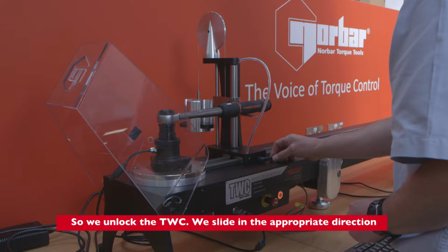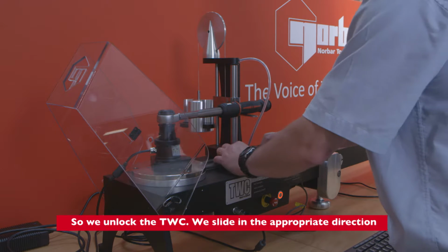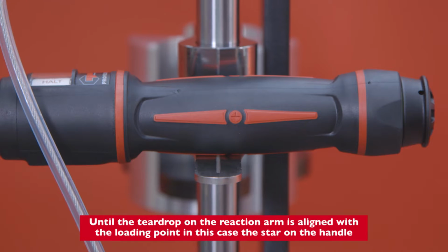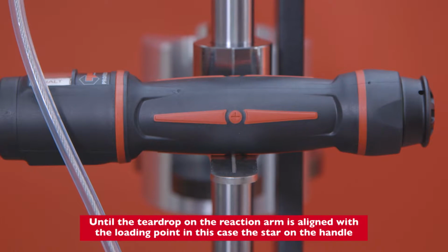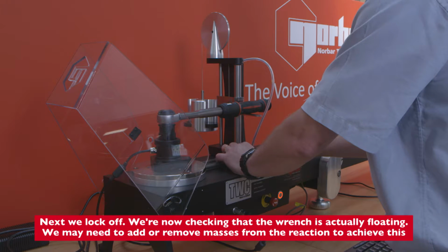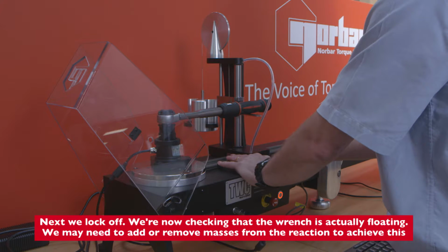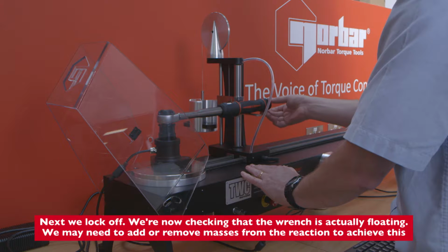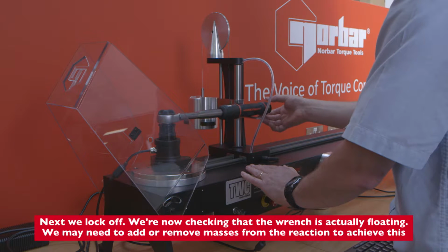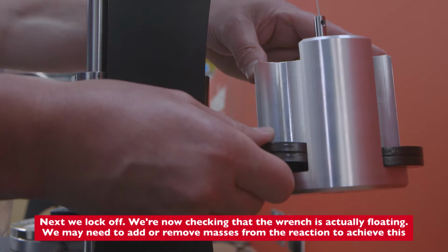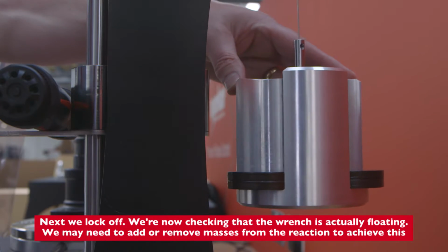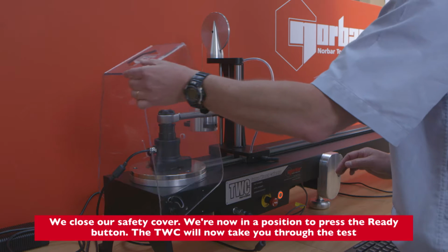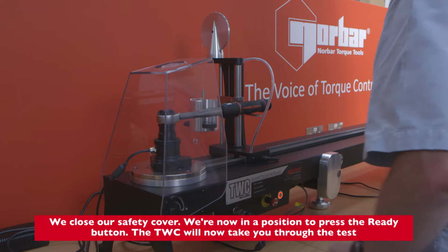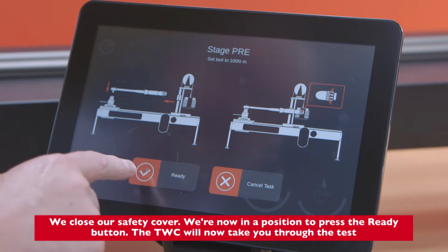So we unlock the TWC, and we slide in the appropriate direction until the teardrop on the reaction arm is aligned with the loading point, in this case the star on the handle. And next we lock off. We're now checking that the wrench is actually floating. We may need to add or remove masses from the reaction in order to achieve this. We close our safety cover. We're now in a position to press the ready button.